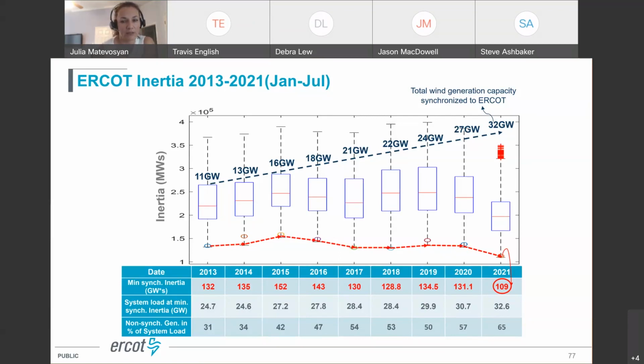We also had, as I mentioned, coal unit retirements, and at the same time, a number of large combined cycles were built. And combined cycles of the same size have up to 1.5 times higher inertia contribution. So you can see in some years, even 2015, 2016 timeframe, inertia actually increased as the amount of inverter-based resources was increasing as well. And so you can see it remained pretty steady.